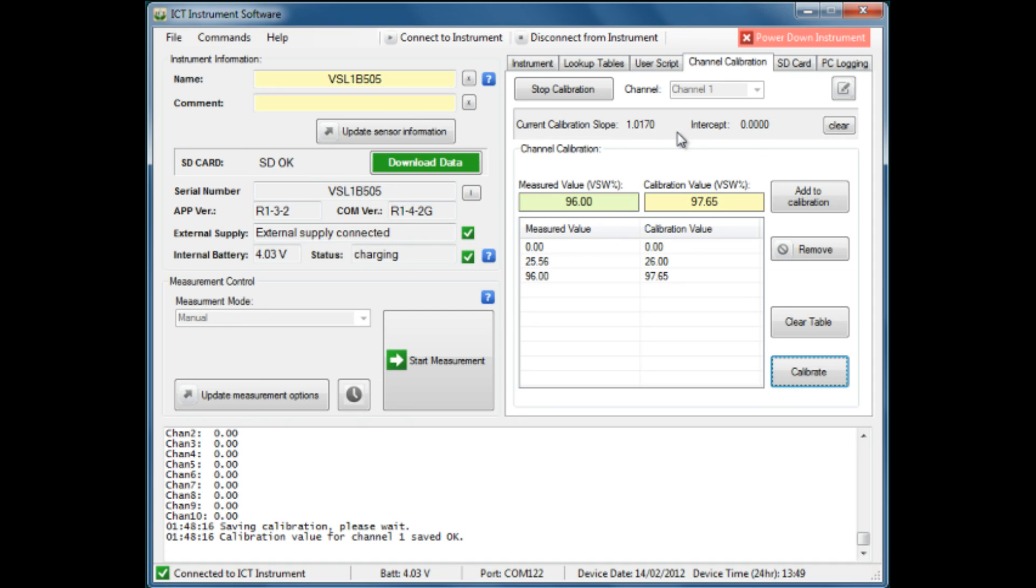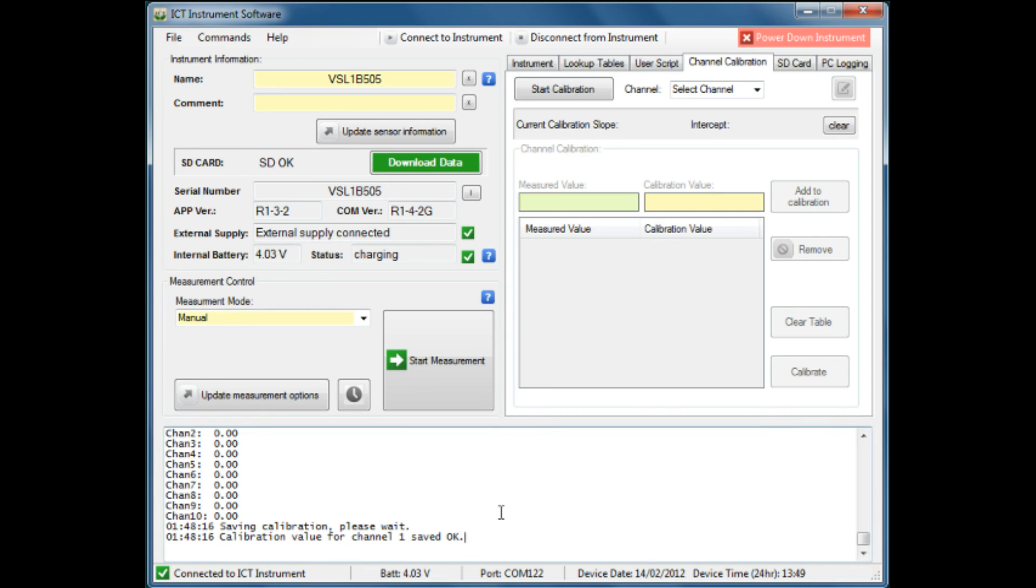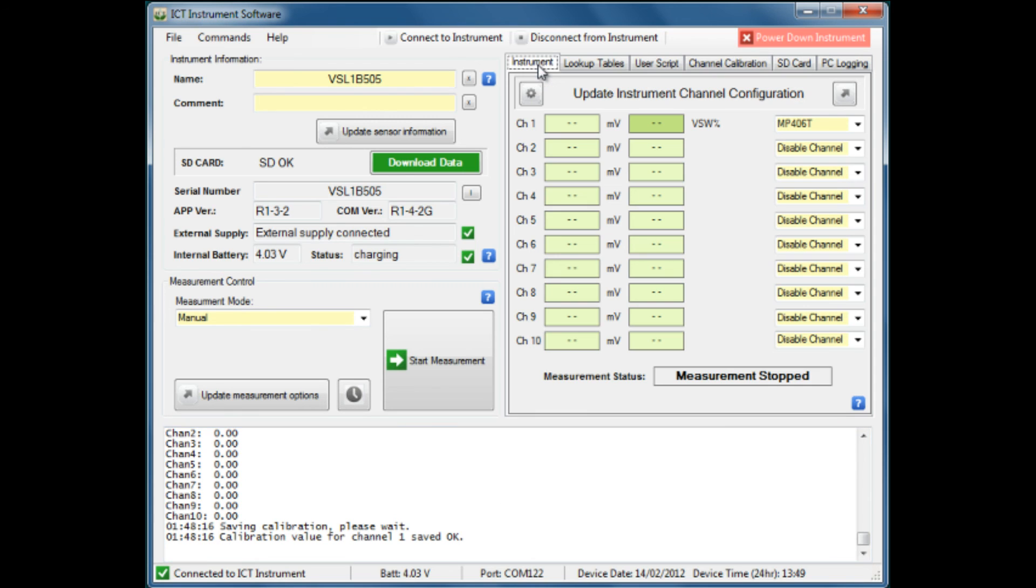We've now finished that, so we can say stop calibration. The channel is now calibrated, and we see down in our dialog box that the calibration value for channel 1 is saved. We have confirmation of that. We can go back to our instrument tab and notice here that channel 1, the results value is a darker green—an indication that that channel has a special correction factor or calibration factor applied to it.